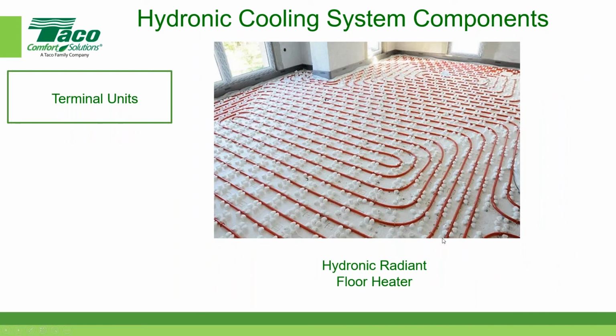I wanted to put this in here. Typically, you would have a hydronic radiant floor heating system, but in some cases, you can actually use chilled water in a radiant floor system. You can take the hot water radiant system and circulate cold water through it as long as the water temperature is above the dew point temperature. And you actually see these types of systems in buildings, especially buildings located in places like Arizona. And I know that Walmart uses that radiant cooling system. I know I have heating here, but I wanted to show you radiant heating. All you need to do is circulate chilled water above the dew point temperature, and you get radiant cooling, which is kind of interesting. So that's another terminal unit that you can use in your system.